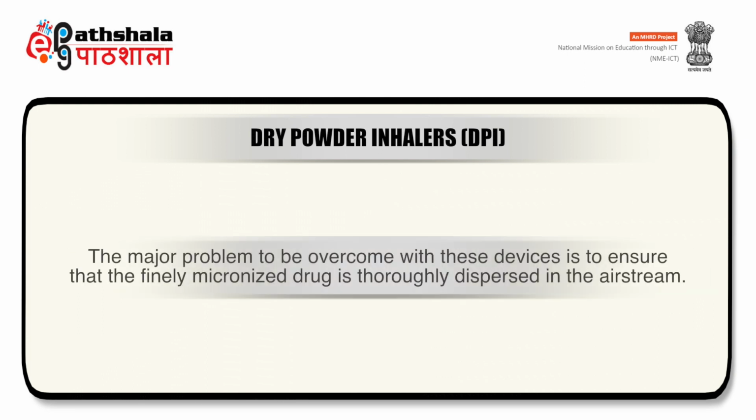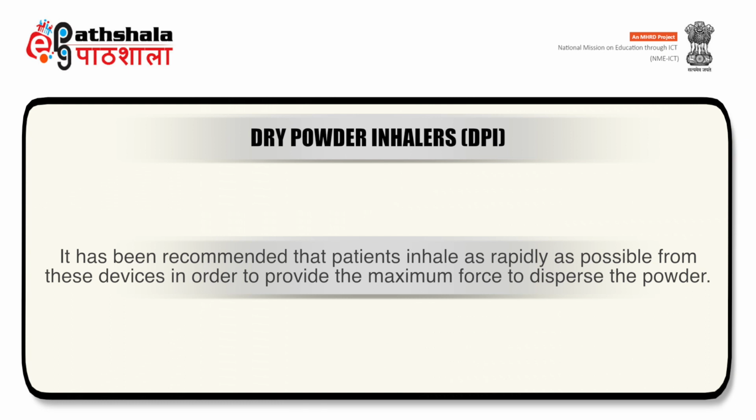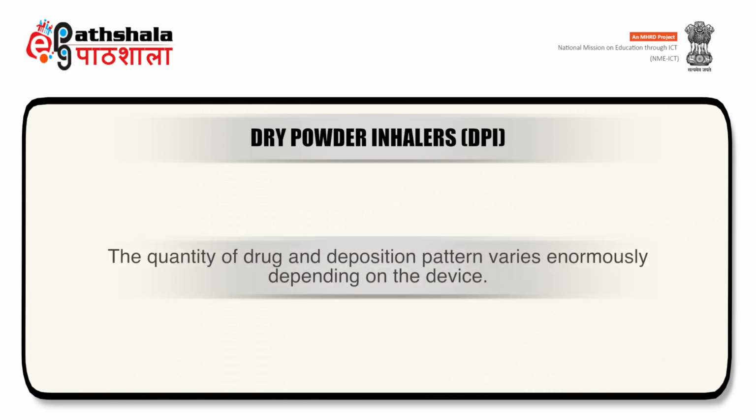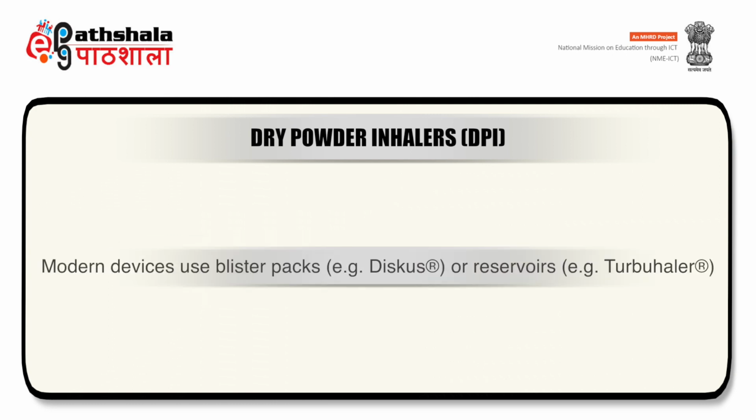The major problem to be overcome with dry powder inhalers is to ensure that the finely micronized drug is thoroughly dispersed in the airstream. It has been recommended that patients inhale as rapidly as possible from these devices in order to provide the maximum force to disperse the powder. Quantity of drug and deposition pattern vary enormously in these devices. Modern devices use blister packs or reservoirs.